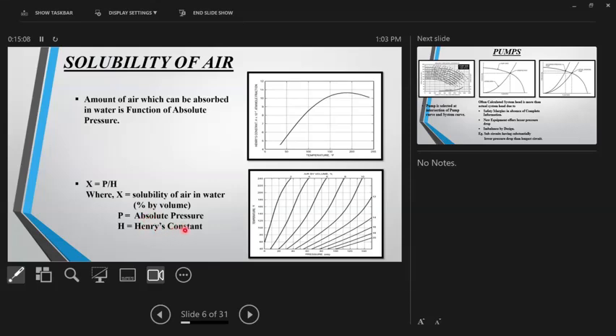Now the Henry's constant, even if we call it a constant, it's not really a constant at a variety of temperatures. It is constant at a given temperature. Let's say you talk about a chilled water system at 8 degree, 10 degree centigrade. If you talk about only one temperature, yes, the Henry's constant is constant. But if you change the temperature, the Henry's constant also changes in an inverted hyperbolic way, right? So this is the graph from ISHRAE about temperature and Henry's constant. So for a given temperature, it's constant. So you can apply this equation for a fixed temperature and can say that the solubility is directly proportional to absolute pressure. So the intent of showing this is that the best location to remove the air from the system is the topmost point, because that's the point where the absolute pressure is minimum.